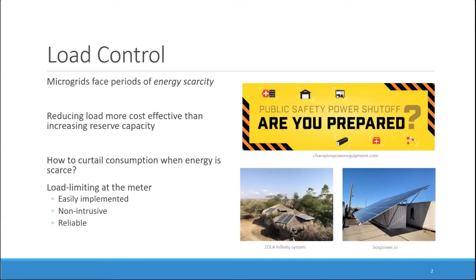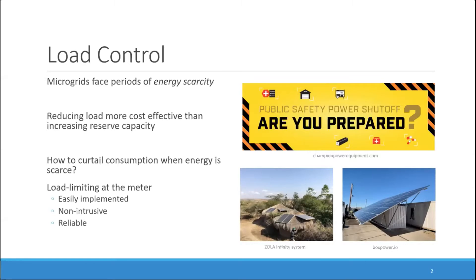Instead, we focus on load limiting at the meter, which is easily implemented by programming meters to disconnect a customer if the load limit is exceeded and broadcasting the load limit to the customer so they can adjust their usage accordingly. This approach is non-intrusive and provides a reliable mechanism of preventing overconsumption.